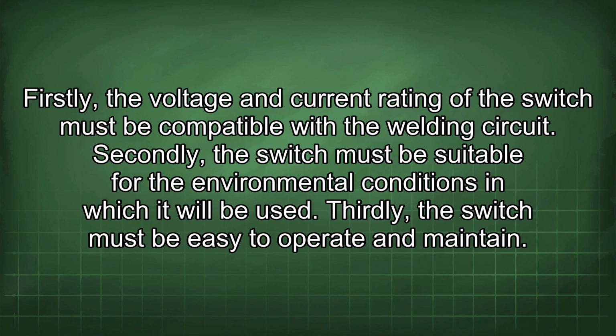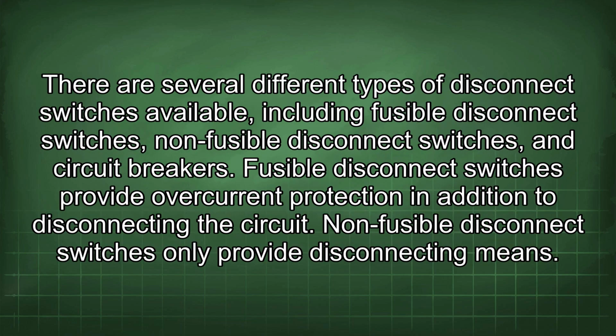Firstly, the voltage and current rating of the switch must be compatible with the welding circuit. Secondly, the switch must be suitable for the environmental conditions in which it will be used. Thirdly, the switch must be easy to operate and maintain. There are several different types of disconnect switches available, including fusible disconnect switches, non-fusible disconnect switches, and circuit breakers.